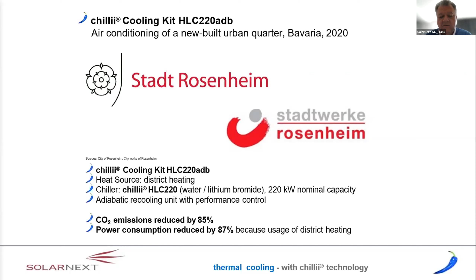They decided to use this heat especially in summertime, since they don't need much heat for households then. So we use it to cool down companies near the plant, with a 220 kilowatt chiller. This application also earned us the Bavarian Energy Award. Rosenheim has since added 3 more machines, now reaching 1 megawatt of cooling capacity nearby. CO2 emissions were reduced by 85% and power consumption by 87% thanks to this district heating use.